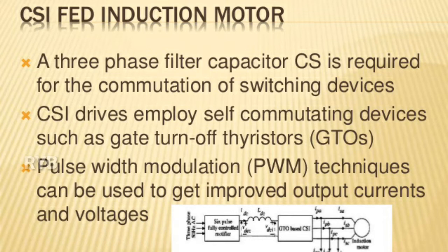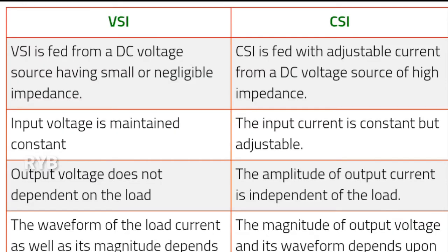Applications include UPS, induction heating, and static VAR compensators. The following table gives a comparative study between CSI and VSI. VSI is fed from a DC voltage source having small or negligible impedance, whereas CSI is fed with adjustable current from a DC voltage source of high impedance.